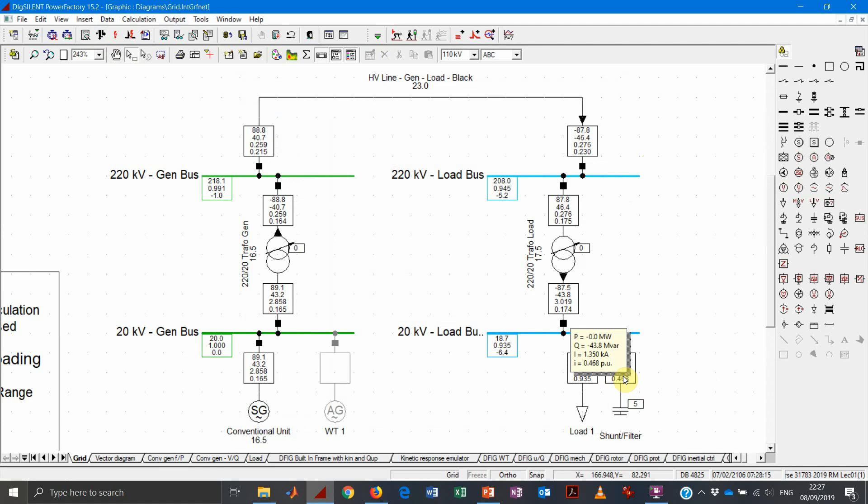You will actually appreciate how these shunt capacitors could be quite dangerous, because they are simple capacitors. Their contributions tend to decrease when the voltage gets lower, and it decreases with a quadratic dependency. And that's exactly the time when you need most of the support.